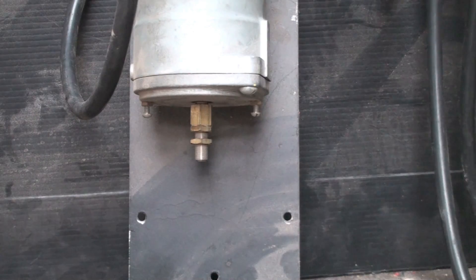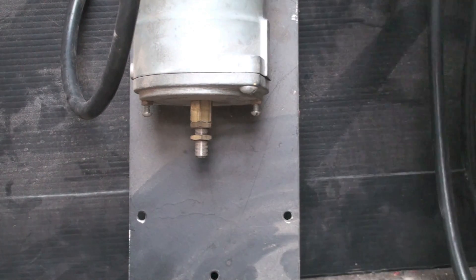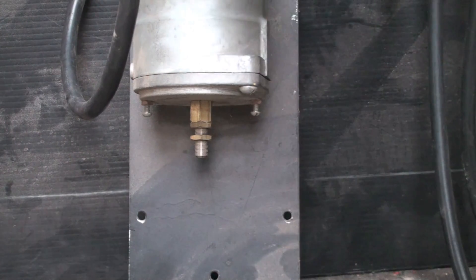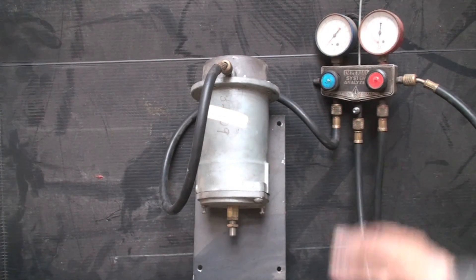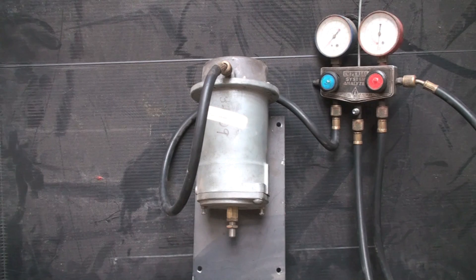When I release that pressure it just dropped out. That's all it is — it's going to go out depending on how much pressure I put in, moving against the spring. That probably controls a damper or something like that. It says fan supply unit, and they're all run by an air compressor — very effective controls.